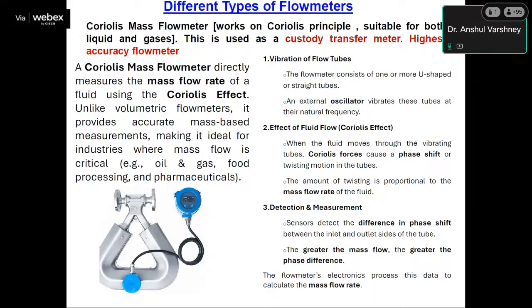Basically, these flow meters consist of the following parts, like vibrating flow tubes. You can see there is a U tube. There are two flow tubes. The flow meter consists of one or more U-shaped or straight tubes. An external oscillator vibrates these tubes at their natural frequency. When the fluid moves through these vibrating tubes, a Coriolis force causes a phase shift or twisting motion in the tube, or you can say there will be some vibration in the tubes. The amount of twisting is proportional to the mass flow rate of the liquid. The sensors mounted on the flow meter detect the difference in phase shift between the inlet and outlet sides of the tube, and this difference in phase shift is directly proportional to the mass flow rate.